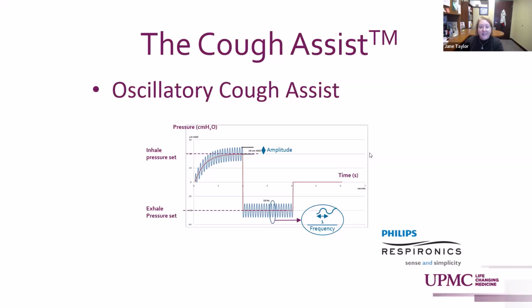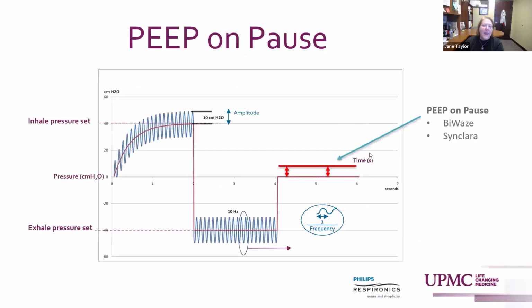And what is nice is that the two newer machines, so the BiWaze and the Synclara, actually have PEEP on pause. And what that is, is some extra pressure that remains, and it doesn't go all the way down to 0. So you can set 4 to 6 for young kids and all the way up to 8 to 10 for older kids. And that just keeps the upper airways open while they're trying to cough the mucus up and out and prevents some malacia.